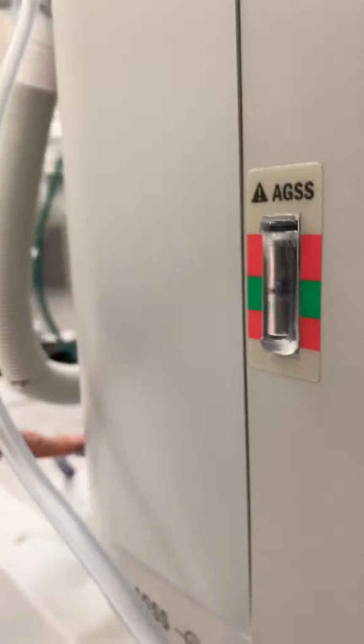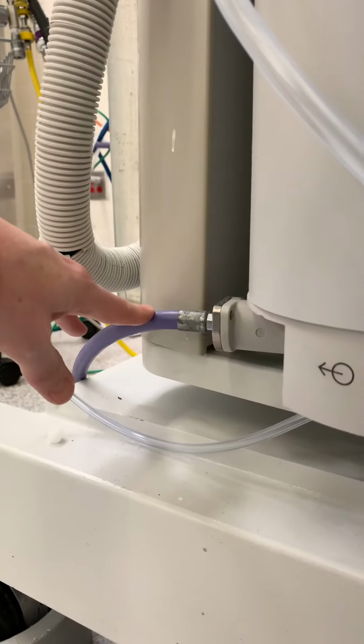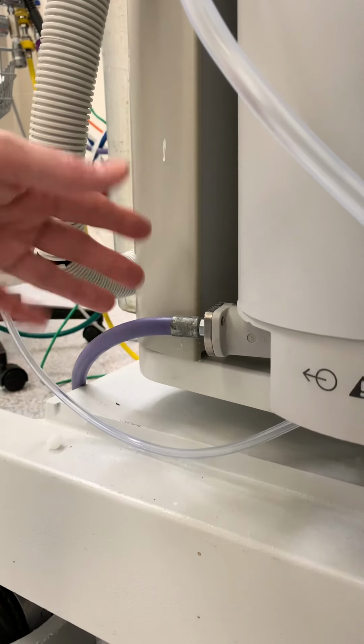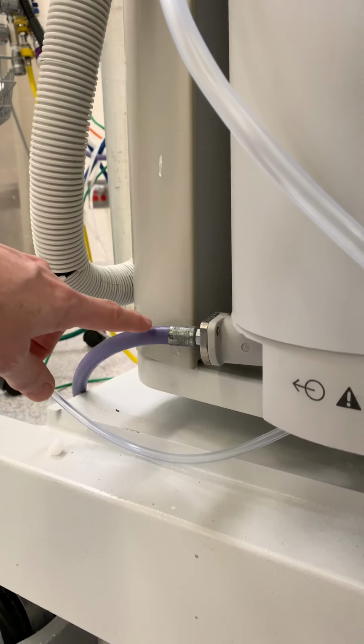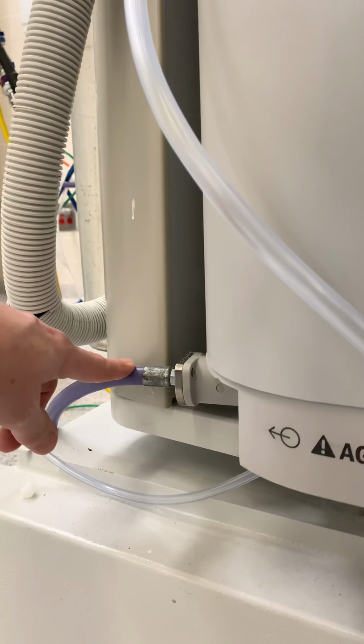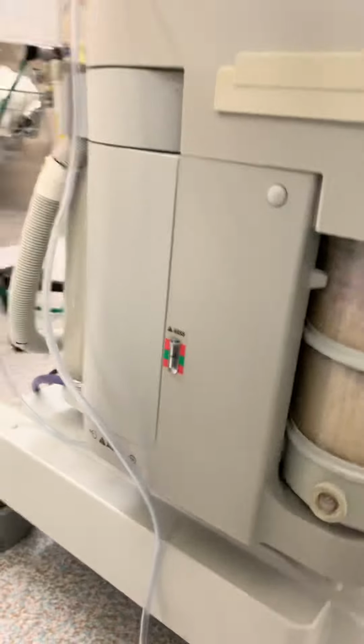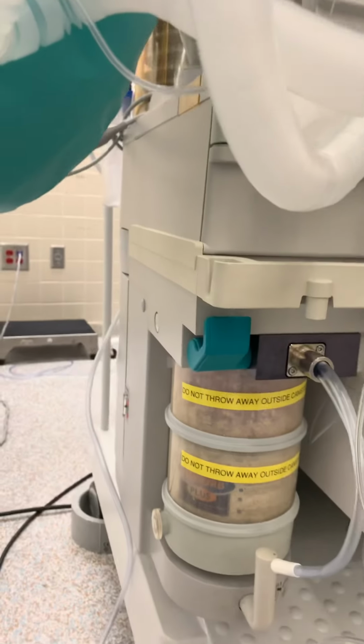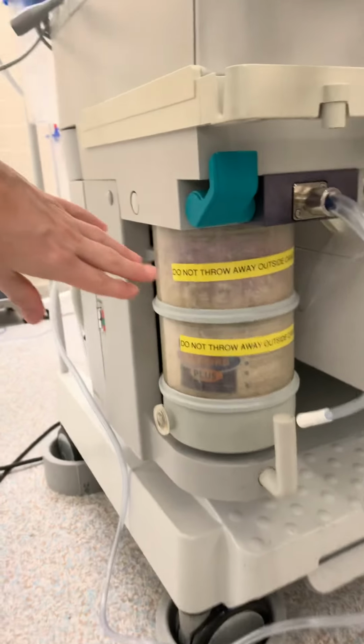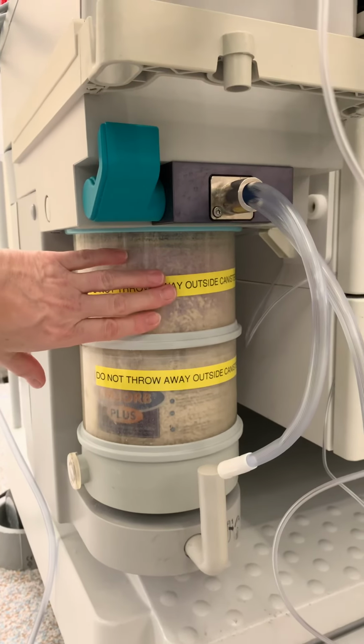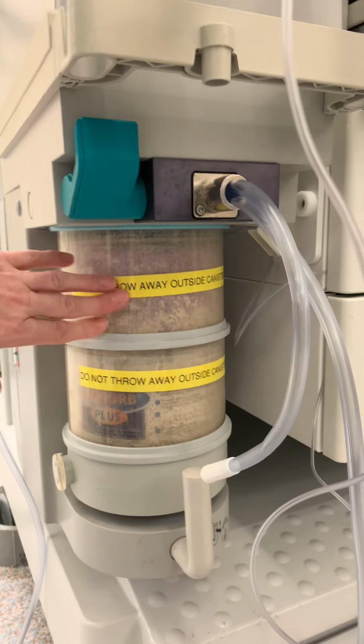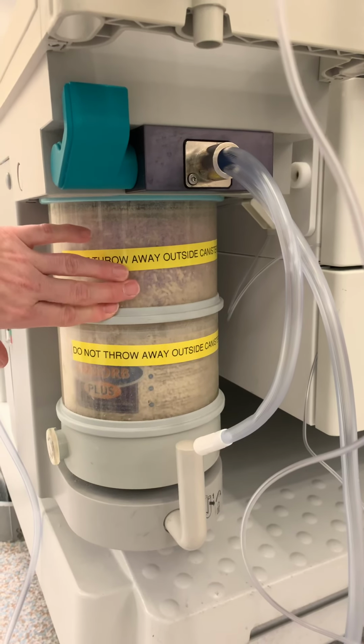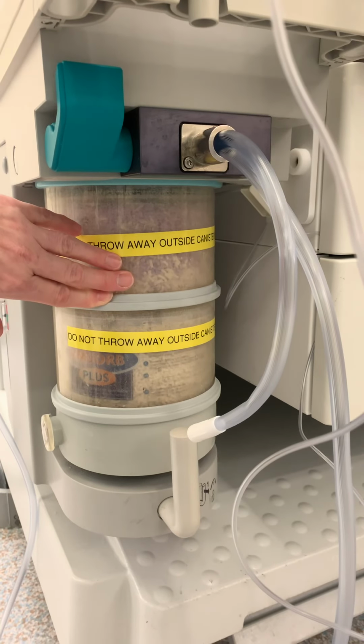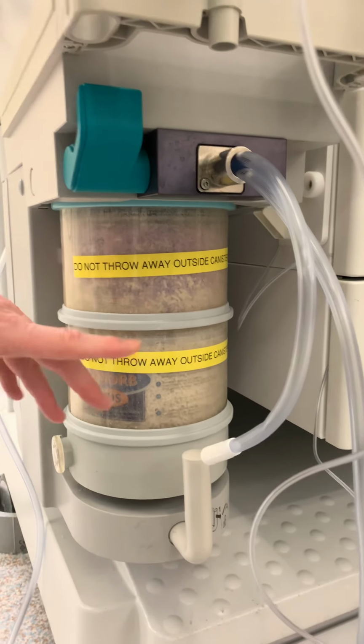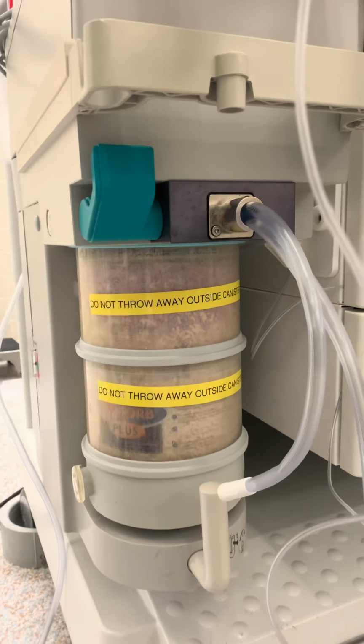And then also you want to make sure that scavenging is connected. Scavenging again is the vacuum, because it's vacuuming gases away so that they don't pollute the atmosphere. So the vacuum again is either a white or a purple pipeline hose, and that is connected. While we're down there, we want to inspect our CO2 canisters, making sure first of all that they're there, that they are white and not exhausted, which would show up in a purple color. These have a little bit of purple, but normally they should look all white, such as these, both of them.